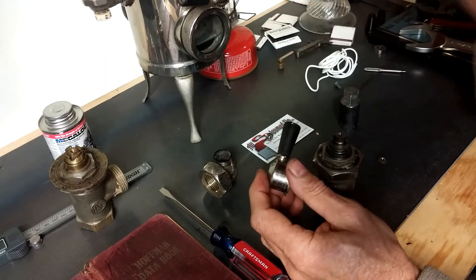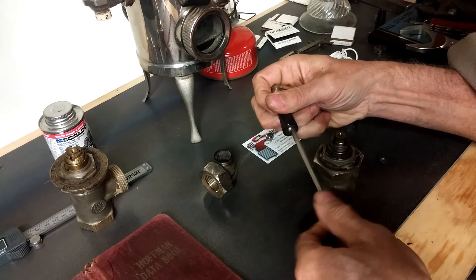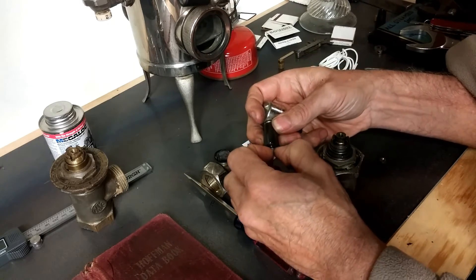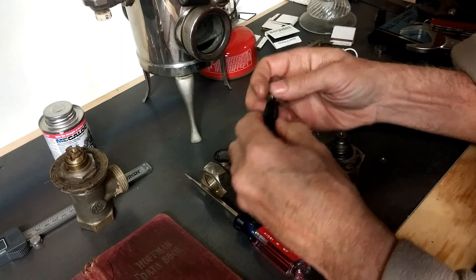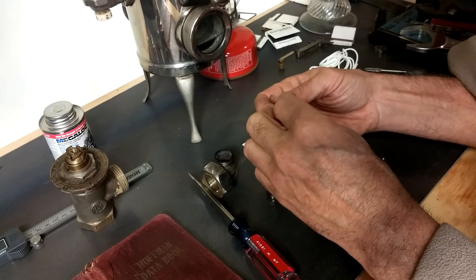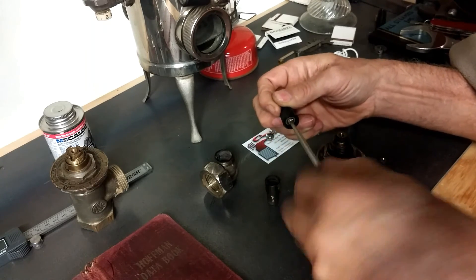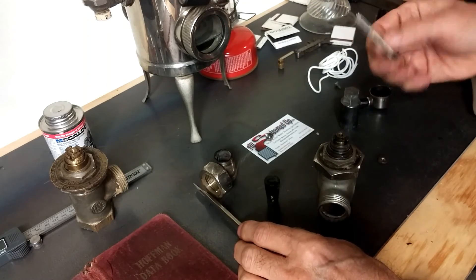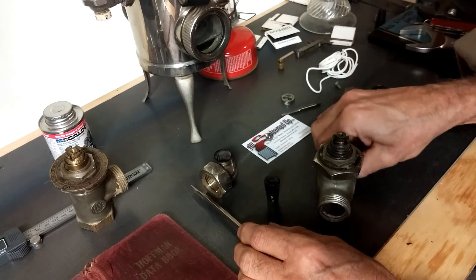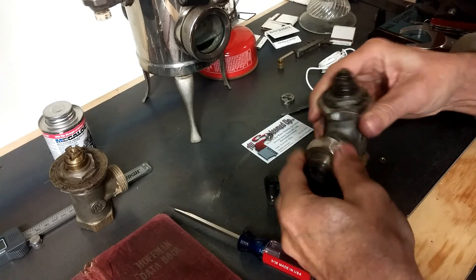If this shield needs replacing, I had a friend scan it, make a digital file, and use a 3D printer to make a replacement out of ABS plastic. This screw here is the same 10-32 threads-per-inch screw, so again I would not lose either one of these items. A 10-32 die wouldn't be a bad idea to include in your kit — you might be able to clean these up to make it work. And that's pretty much your basic introduction to the Hoffman Number 7 modulating valve.